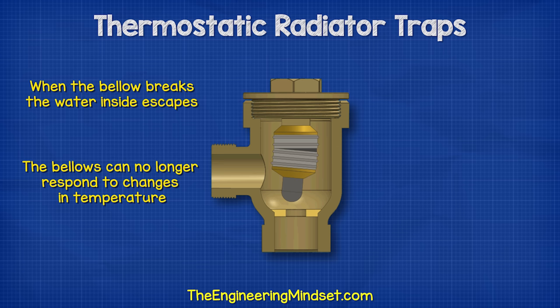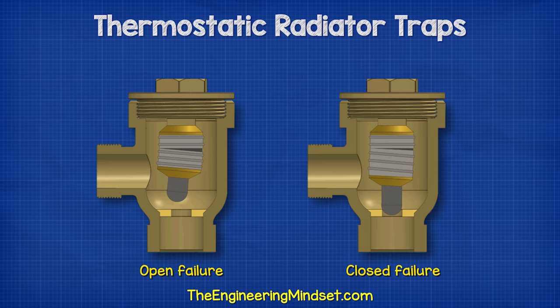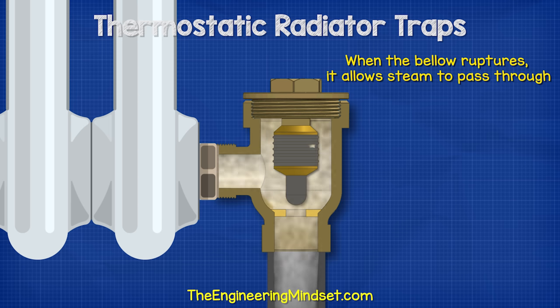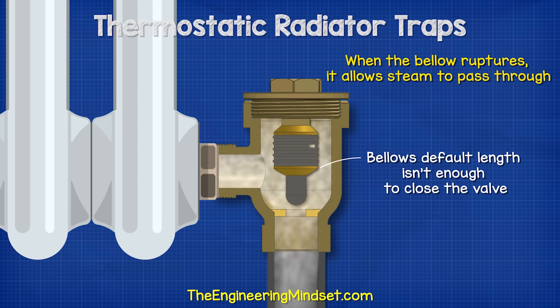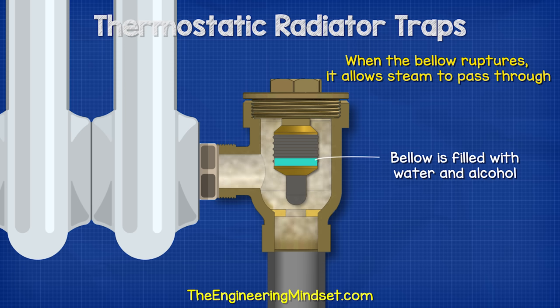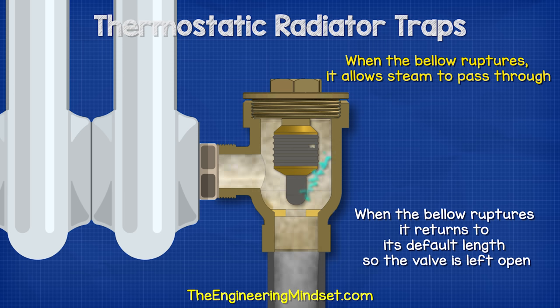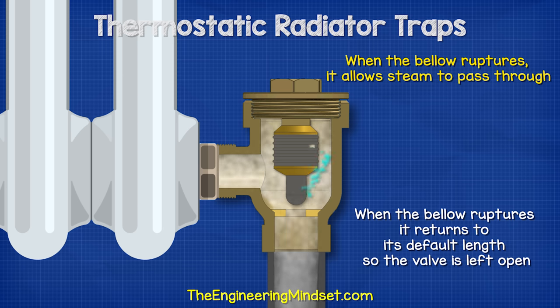When bellows fail, the trap can either fail open or closed depending on the type of construction. With an open failure, when the bellow ruptures it allows steam to pass through. This occurs because the bellow's default length isn't enough to close the valve — the bellow is filled with water and alcohol which expands and forces it past its default position. When the bellow ruptures it returns to its default length, leaving the valve open. This allows steam to flow through, wasting energy and causing problems in the system.